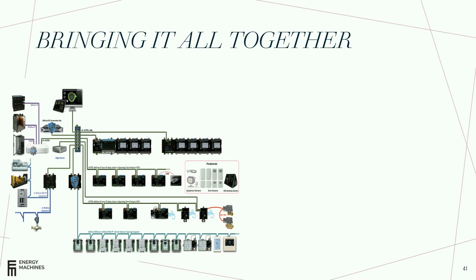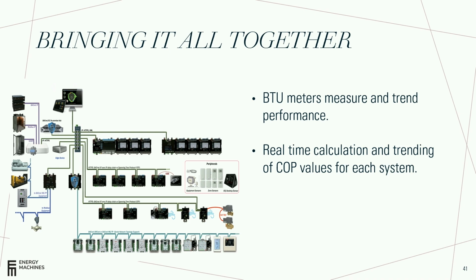With the BMS system, a lot of the magic happens here with controls. You have BTU meters measuring the performance. One thing I'd advise all engineers to do is have real-time calculations on the COP of the system. I've read thousands of specs and never seen it once, and it's an easy thing to do—it'll tell you how your building is actually performing.